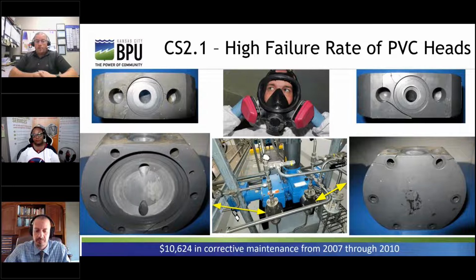In our system, we have 2 mechanical diaphragm pumps, 2 heads on each pump for feeding of aqua ammonia into our finished water to produce monochloramine for EPA's disinfection requirements. The failure rates for these heads was several times a year, and a HAZOP RPM study recommended that the PVC components exposed to aqua ammonia should be changed to stainless steel.